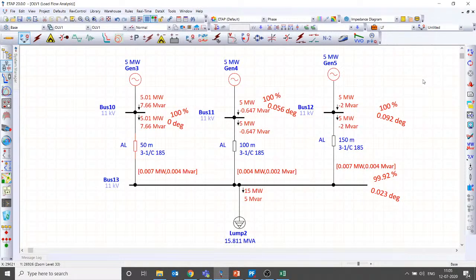There is no change in the real power, but imagine the change in the reactive power. There's a huge reactive power mismatch, and that's all because of the cable length. Even if you are able to match the real power, you cannot match the reactive power. We expect all the generators to share equal reactive power, but that's not practically possible if you have different cable lengths. In reality, if you have two or three generators on a common switchboard, there will always be a difference in cable length.